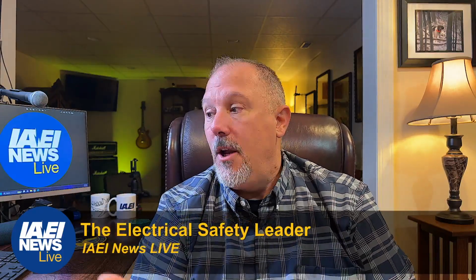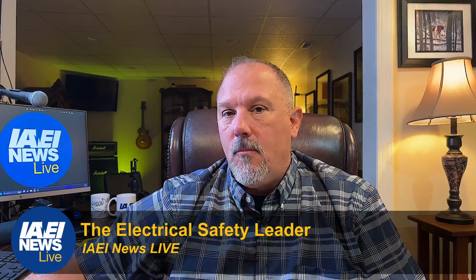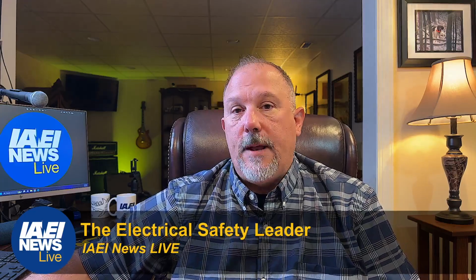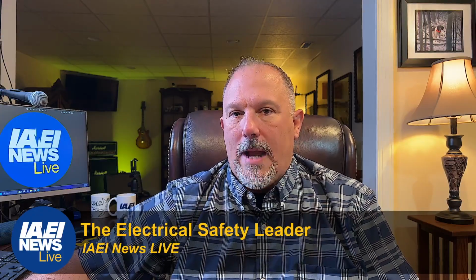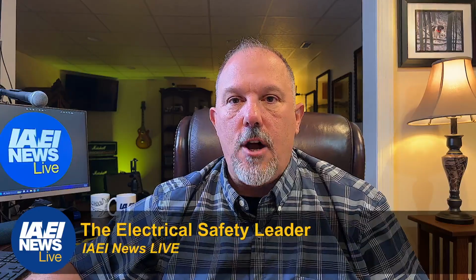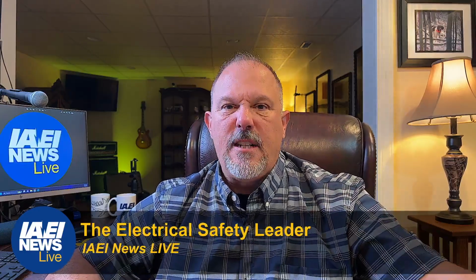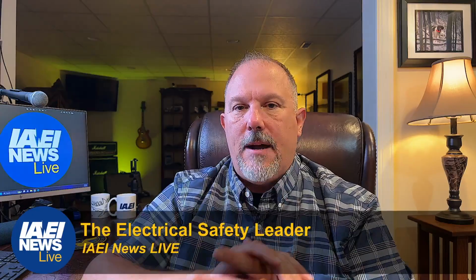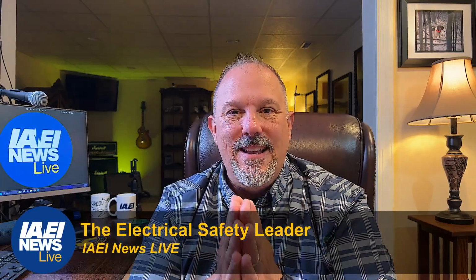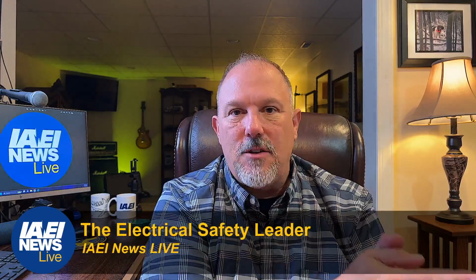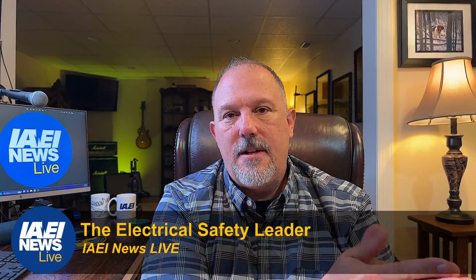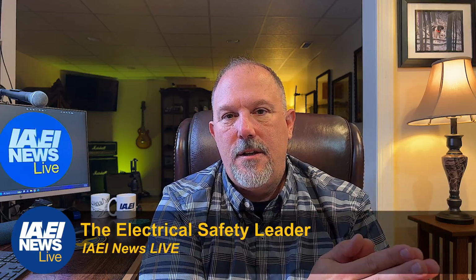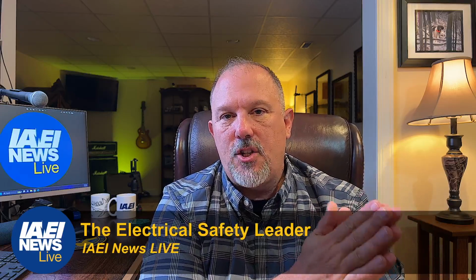Should you look for that? Probably. Should there be something in here that's a little bit more prescriptive in regard to your visual inspections, making sure you don't have multiple grounds in a power distribution system? Make sure you're not connecting the grounded conductor with the grounding conductor throughout the power system. Maybe, but that would mean you didn't follow the installation requirements, because the installation requirements is what helps us make sure that we don't do those things.